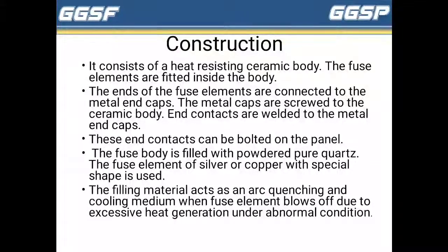The fuse body is filled with powdered pure quartz. The fuse element is of silver or copper with special shape. The filling material acts as an arc quenching and cooling medium when the fuse element blows off due to excessive heat generation under abnormal condition. Main advantage of the HRC fuse is that it is easy to install and has high breaking capacity, but the disadvantage is that these fuses can't be reused.